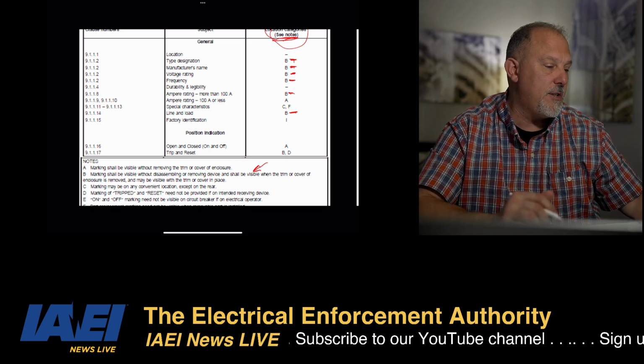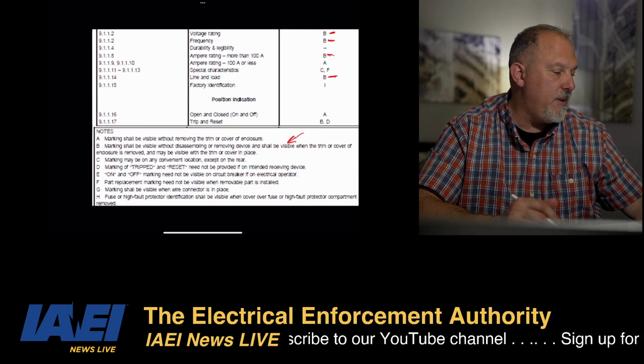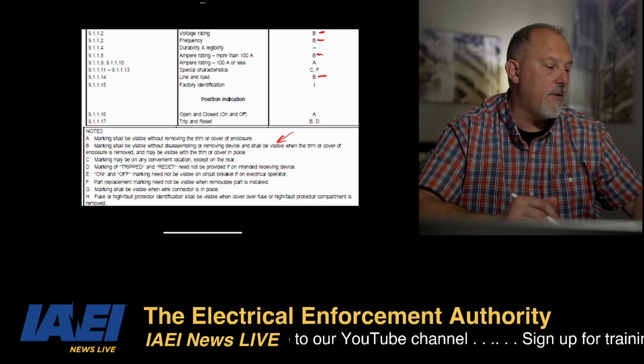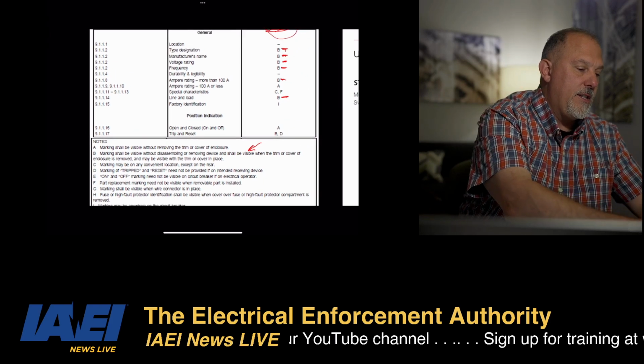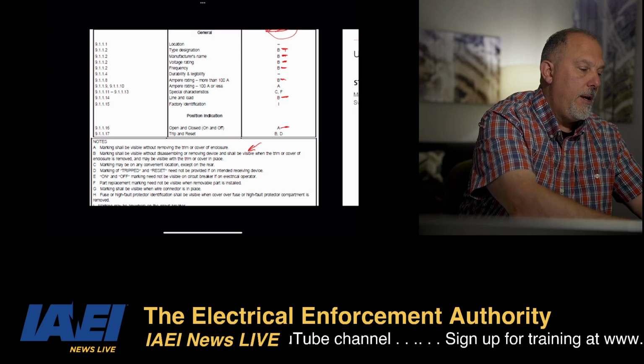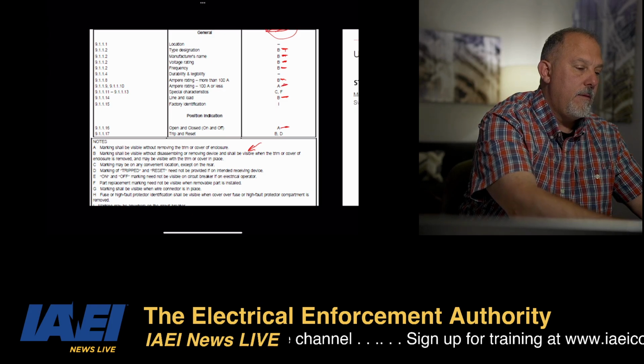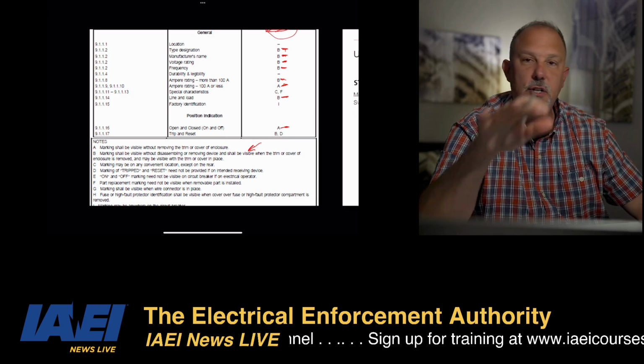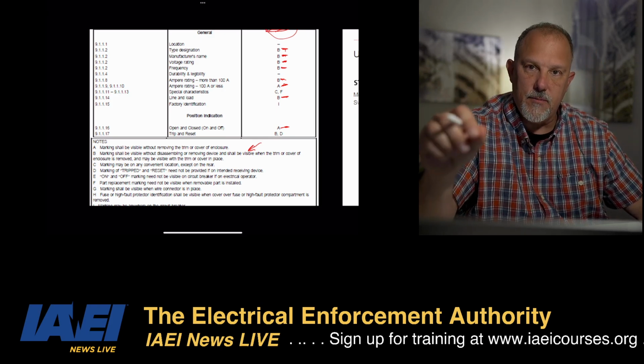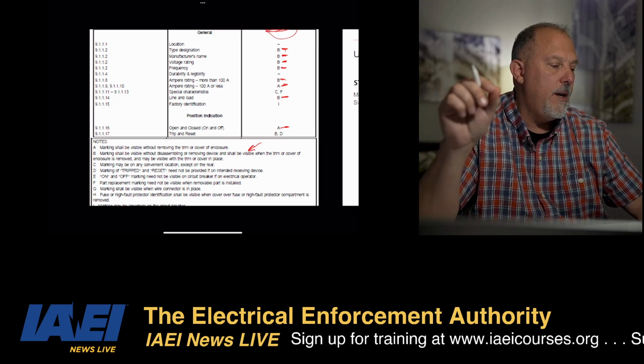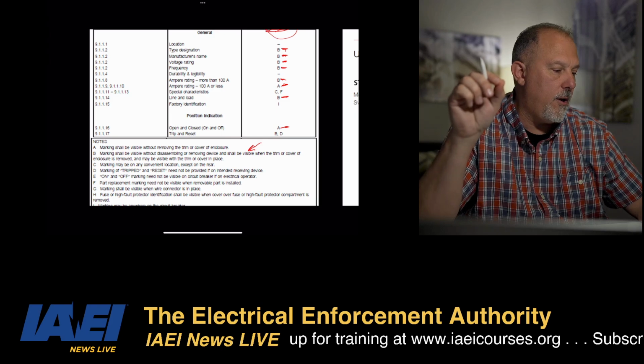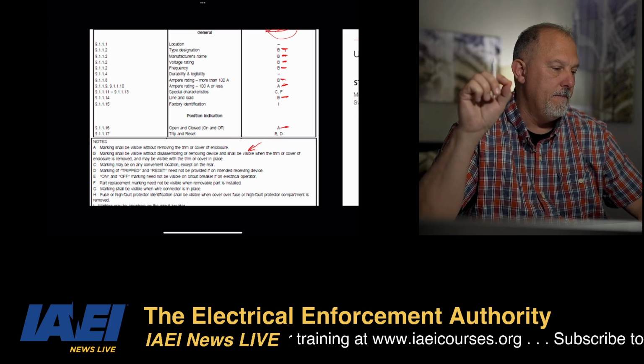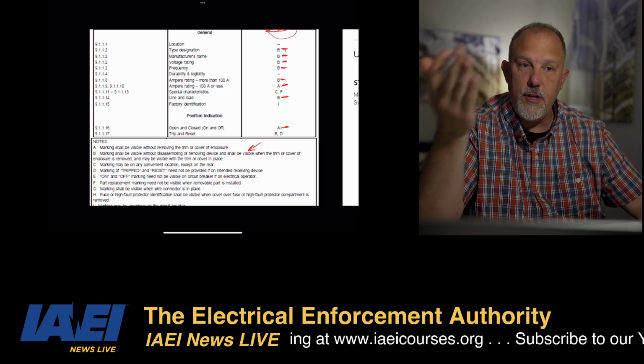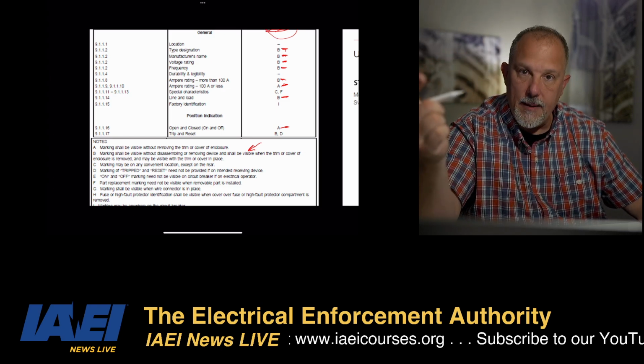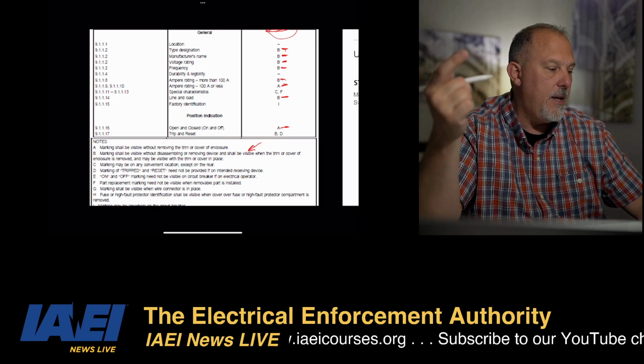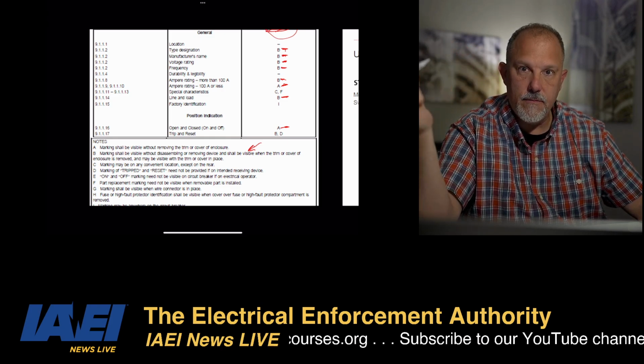So that's locations B. What is A? Marking shall be visible without removing the trim or cover of enclosure. So that is the open and closed, and that is the ampere rating. Those are the only two items that have to be visible without removing the trim, cover, or enclosure. So basically you open the door and you need to be able to see what the ampere rating is for 100 amps and less, and then what is on and off. Okay?